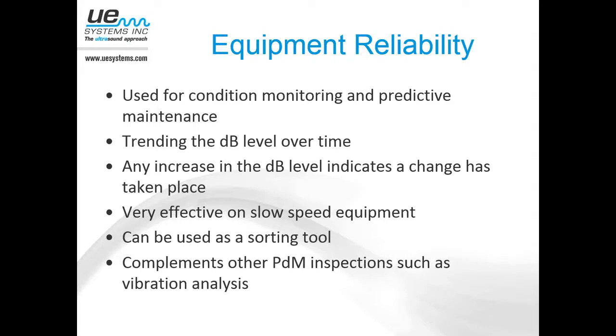One of the things we do is trend these decibel levels over time. We set up a program, pick out which assets need to be on the route, and go test them, usually on a monthly basis, very similar to vibration analysis. Any increase in the dB level would indicate some kind of change has taken place. We like to set up alarm levels, which I'll talk about in a second. From a trending standpoint, we want to watch what that asset does over time and make appropriate decisions based on what we see.